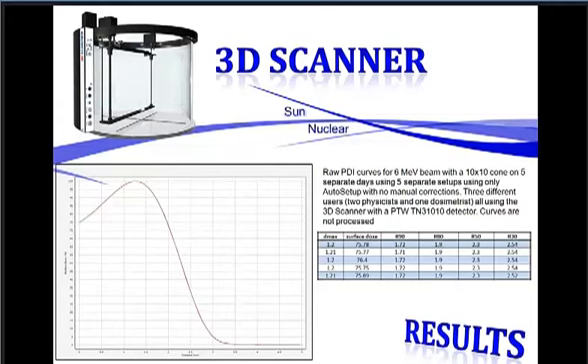So you can see R90, R80, R50 there. D-Max essentially and the surface dose readings in the table for a little bit more clarity. But as you can see, the auto setup user to user, day to day, condition to condition is relatively impressive, at least in our opinion.